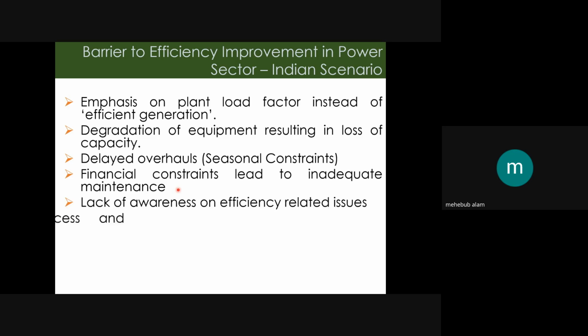Now, these are the various parameters that we have to observe in a thermal power plant to maintain efficiency and energy utilization at an optimal level. But in spite of this, there are so many barriers, because generally we focus on the plant load factor, meaning how many hours the plant is generating, and every utility is trying to maximize the plant load factor instead of efficient generation.